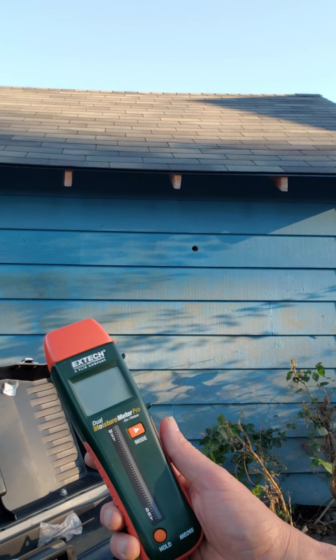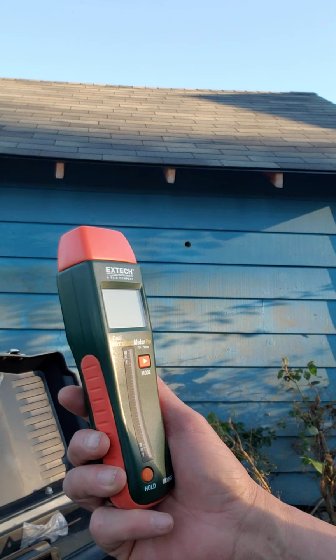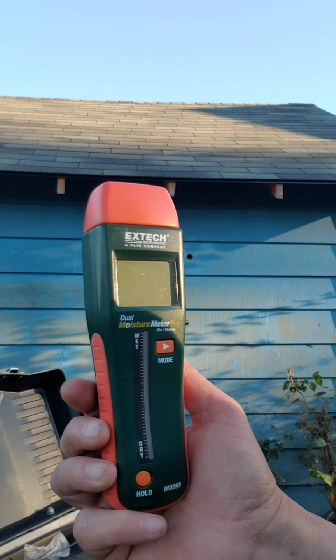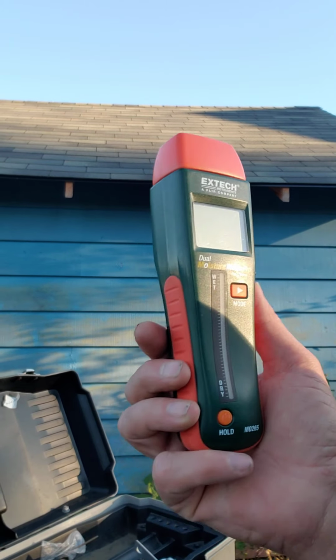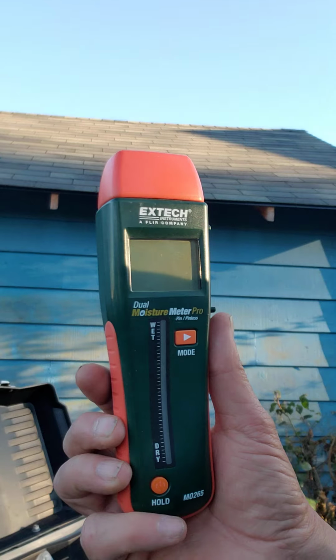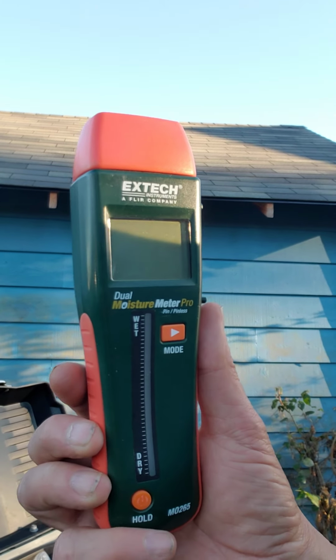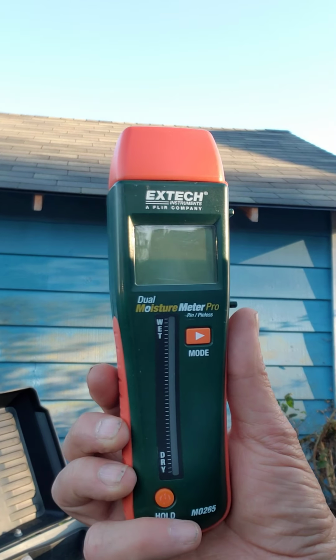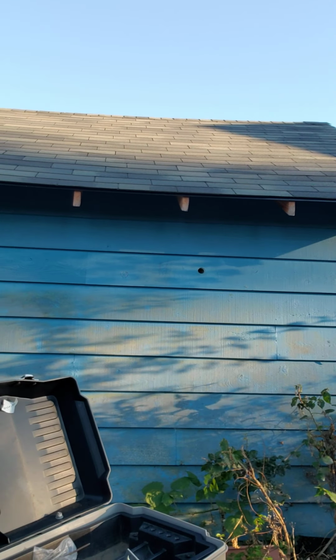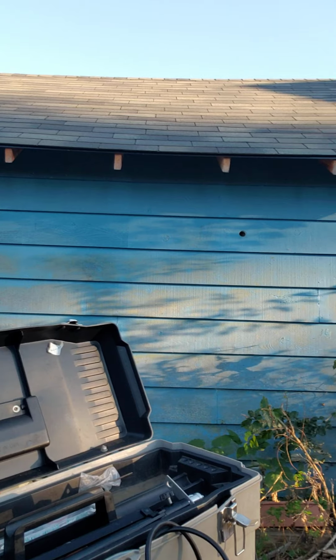This is my moisture meter, one I've used for many years from Extech. I've probably gone through 6 or 8 of these. We can use the pin or the pinless to figure out what moisture level is in the substrate. I use these a lot in attic spaces to see what the middle of the wood looks like, how wet it is.